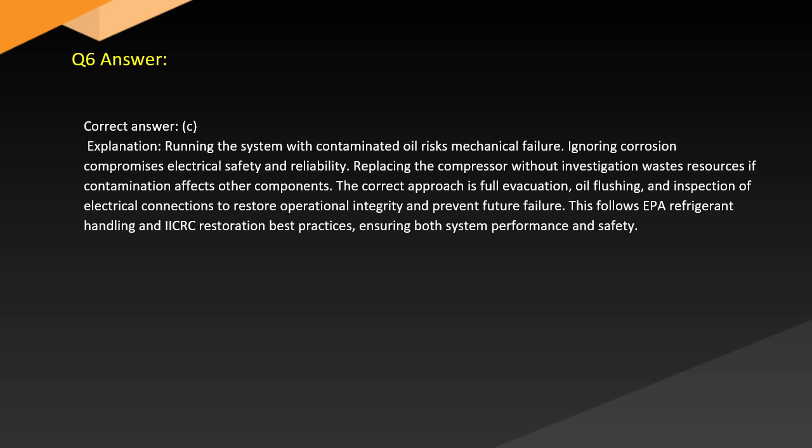Answer. Correct answer: C. Explanation. Running the system with contaminated oil risks mechanical failure. Ignoring corrosion compromises electrical safety and reliability. Replacing the compressor without investigation wastes resources if contamination affects other components.